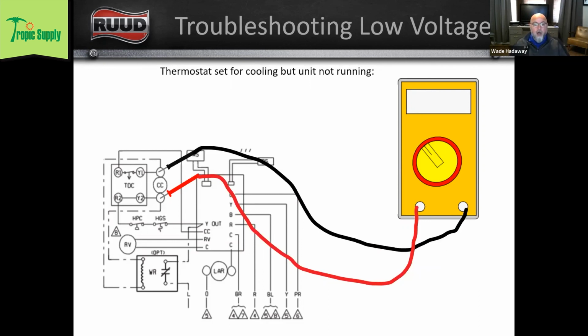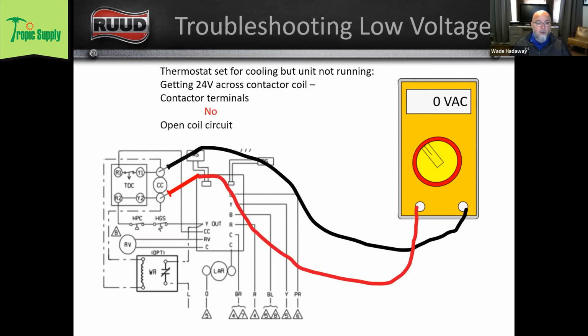We check across our contactor coil. Are we getting 24 volts? Are we seeing a 24 volt drop across our contactor coil for those terminals? And in this example, no, we're not. So we have an open circuit. Now it says open coil circuit because right now it could be, right?